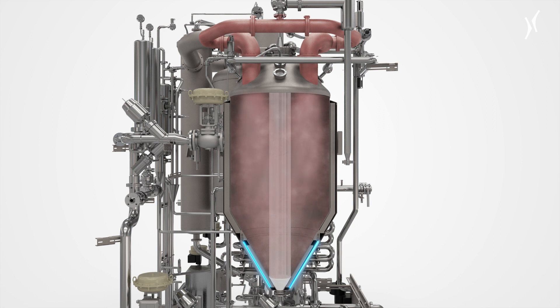A big benefit of this technology is that we have very rapid heating and cooling time. The product is not heated by heat transfer in a tubular heat exchanger — we heat it by means of condensation. This means hot steam will condensate in cold product, and we can do this during a free fall in an infusion chamber. The product enters the tank at the top, falls down through a steam chamber, and reaches during the free fall a temperature of 150 degrees.